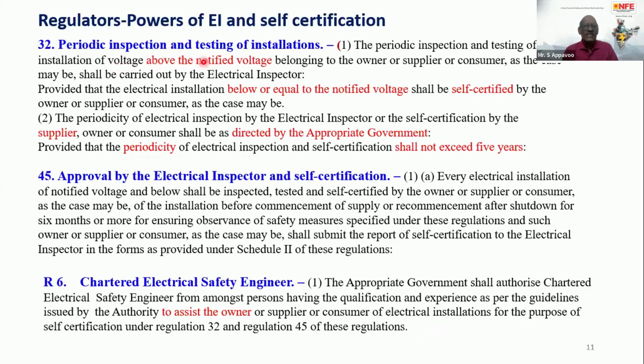How? For which they have fixed some notified voltage. As per Regulation 32, the state government will declare the notified voltage. It varies, actually, in our country. It is 11 kV in certain states and 33 kV in certain states. But the roles of the electrical inspector and the chartered electrical safety engineer are defined by this notified voltage. That means for an electrical installation below or equal to the notified voltage, self-certification comes into effect. So the owners can self-certify their installation by utilizing the chartered electrical safety engineers.